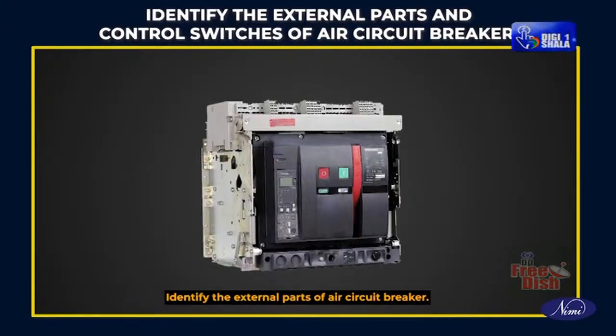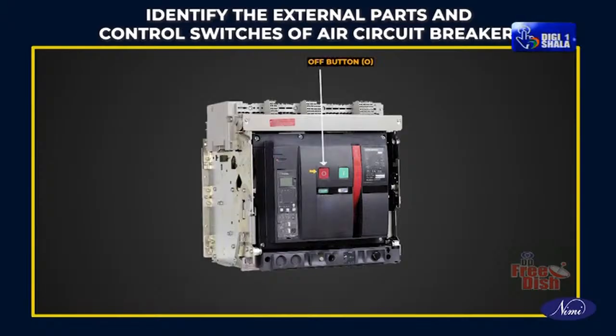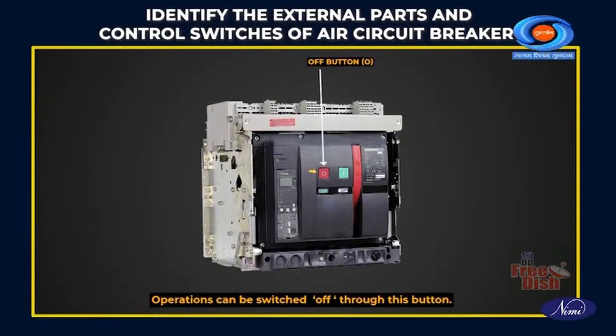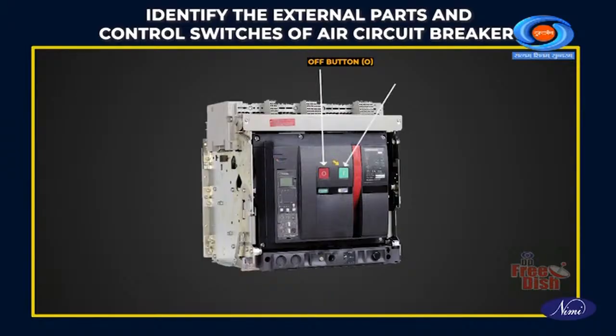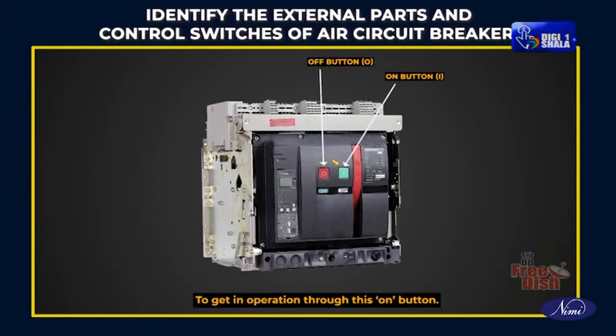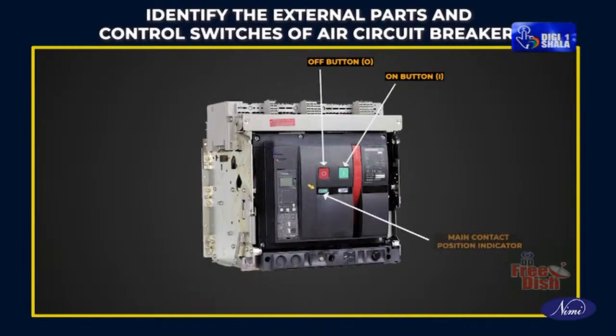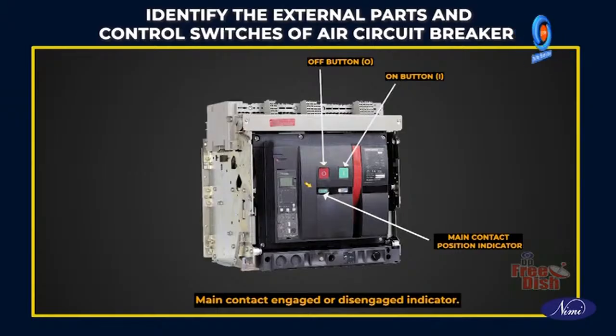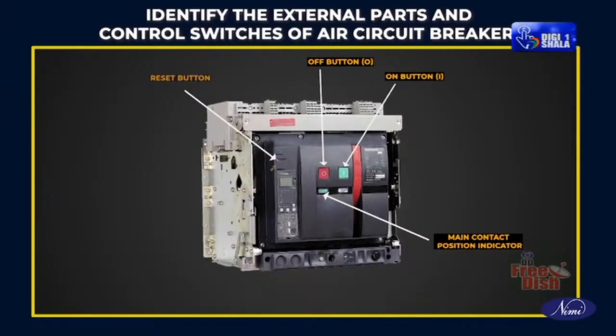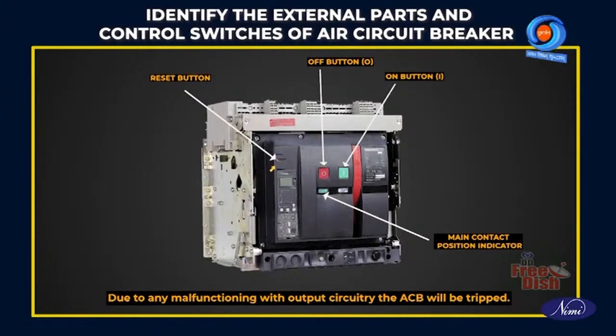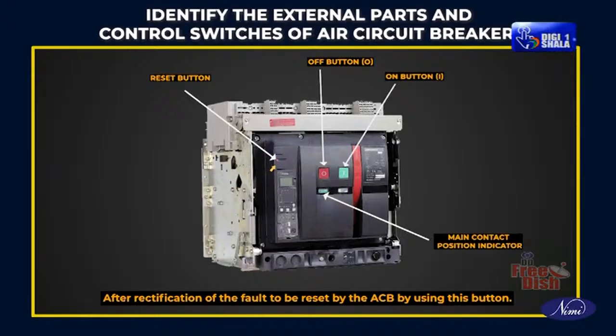Identify the external parts of the air circuit breaker. Off button O: operations can be switched off through this button. On button I: to get into operation, use this on button. Main contact position indicator: indicates main contact engaged or disengaged. Reset button: due to any malfunction in the output circuitry, the ACB will be tripped. After rectification of the fault, the ACB is reset using this button.